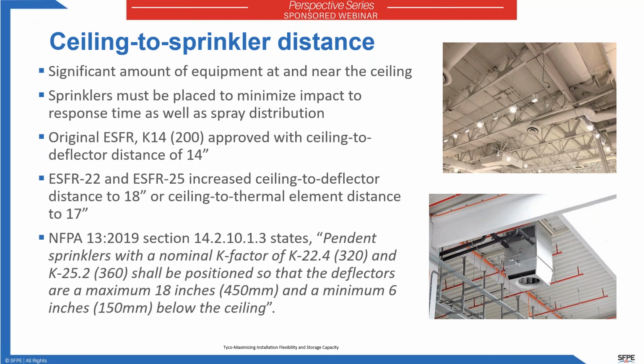One of the attributes with regard to sprinkler installation is putting the sprinklers somewhere up in the ceiling. That's why there's a lot of installation rules. So if you go to NFPA 13, the installation chapters talk about where these sprinklers are located, how they get located relative to obstructions. You walk into a warehouse and you look up, there's a lot of things on that ceiling besides just sprinklers. Me as a sprinkler guy, I want to walk up there and I just want to see a clean line of sprinklers and everything out of the way, but that's not always the case, right?